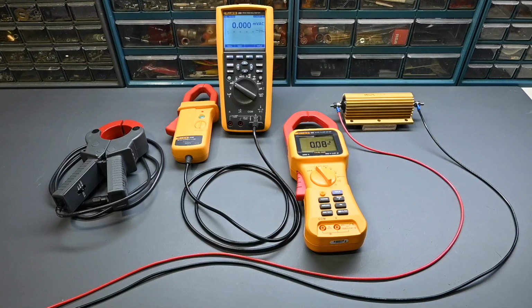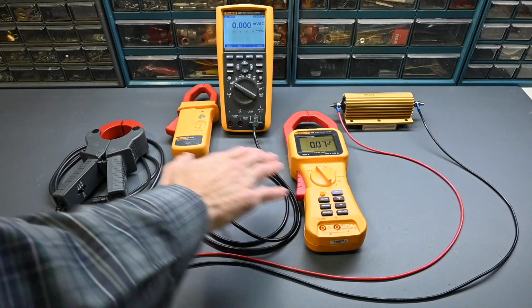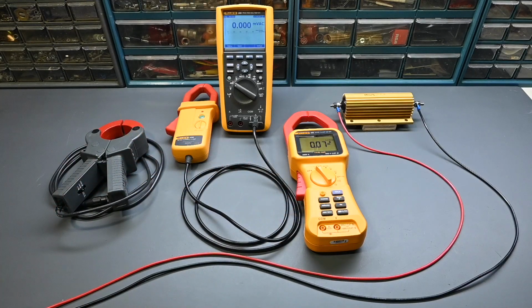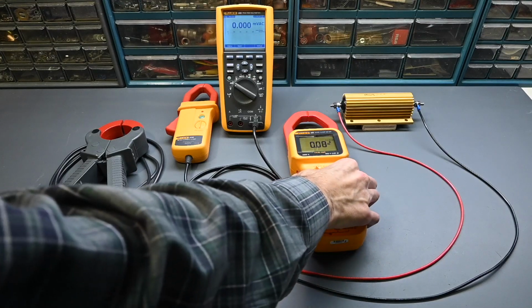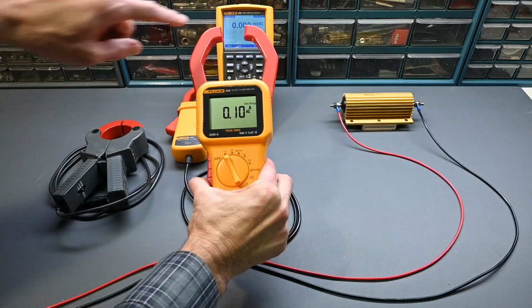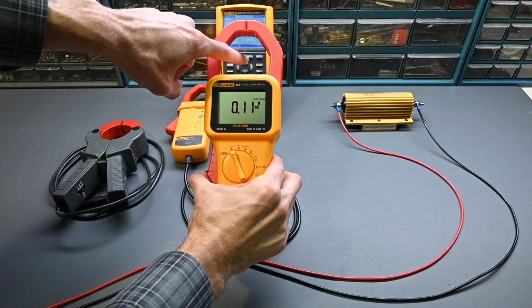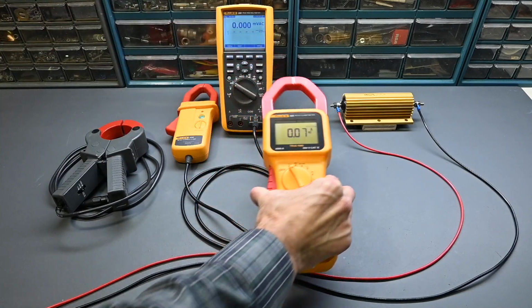So current clamps are another way to take a current measurement. I have 3 different examples here. So current clamps work by sensing the magnetic field around the conductor, and they're extremely easy to use because they don't require breaking into the circuit like we did with the current shunt to take the measurement. So take the current clamp, just open the jaws of the clamp, put the conductor into the center, close the jaws, you're able to take the current measurement, just that simple.